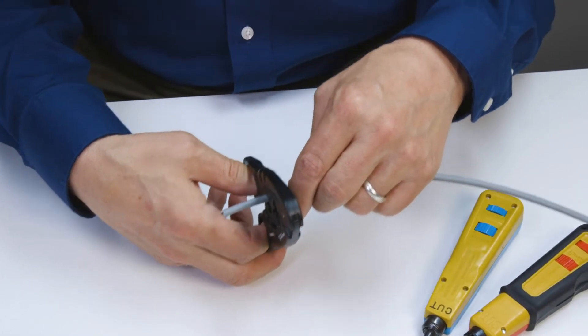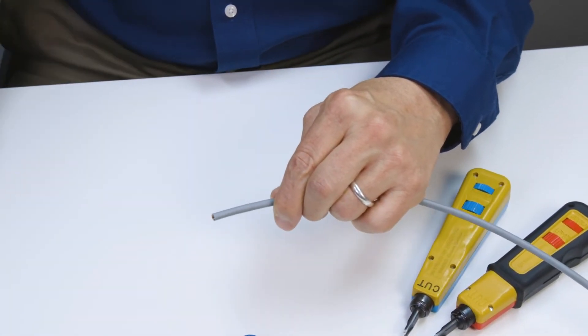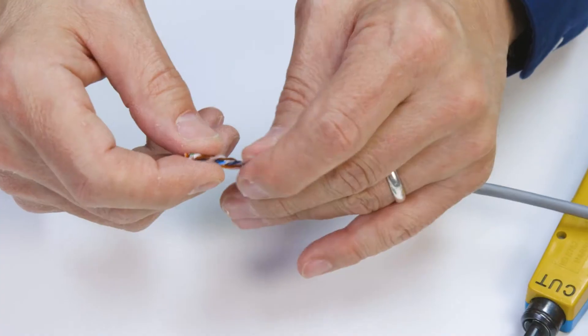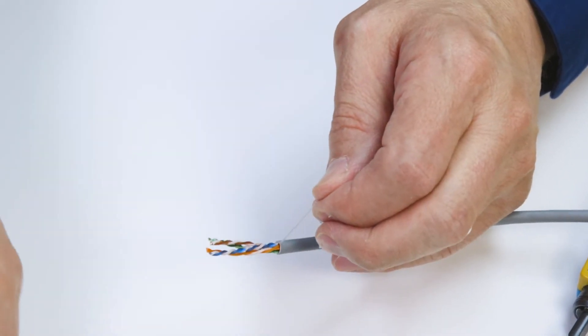With a data wire strip tool, set the proper depth and go around once so that you don't cut into the conductors. Next, break the cable at the strip point and remove the jacket. Now remove the strip string and any other non-conductive elements with a flush cutter.